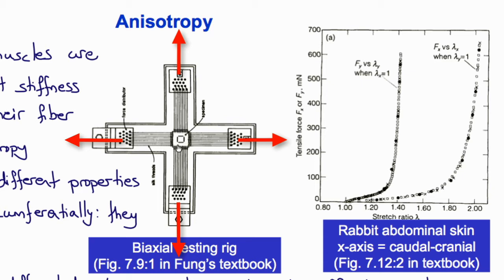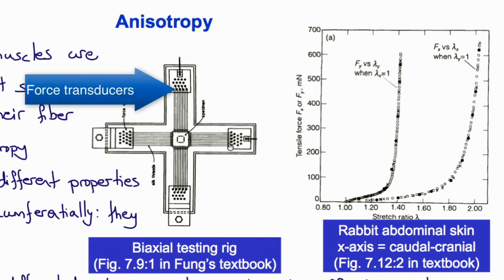Usually in a biaxial test device like this, the strain is measured by visualizing the displacement of markers in the middle of the specimen away from the tethered edges. The test device pulls equally in both directions to keep the specimen centered, but doesn't have to pull equally in both directions, so a variety of different multi-axial stretch ratios can be applied. Force transducers are attached to these strings, and so the forces can be divided by the cross-sectional area to obtain the stresses.